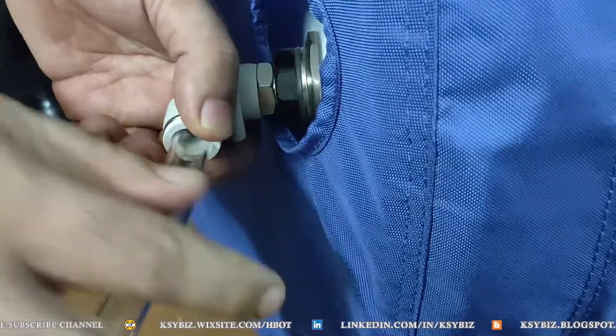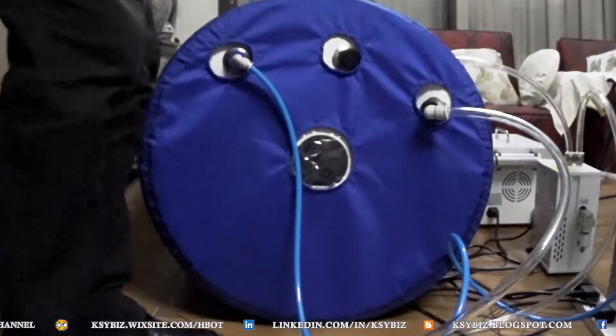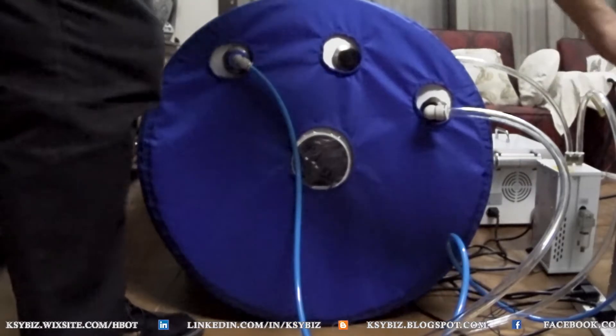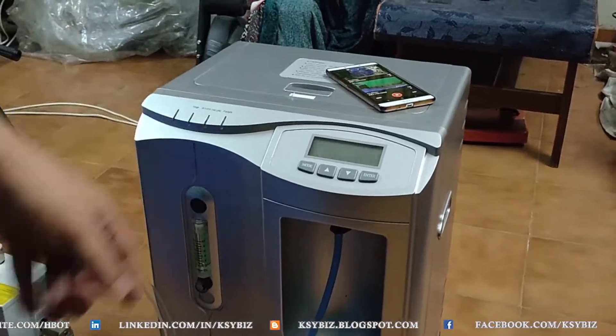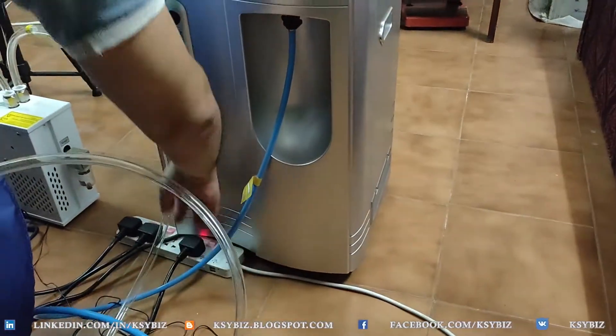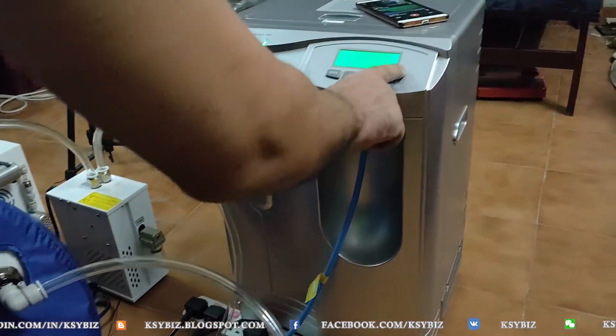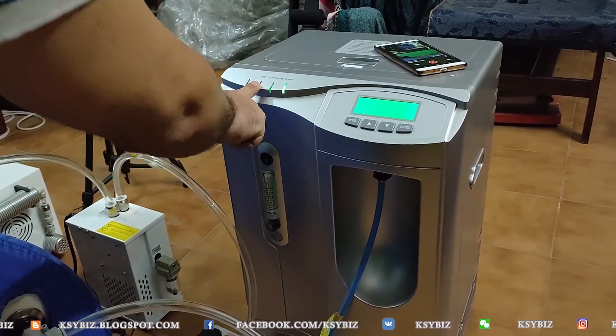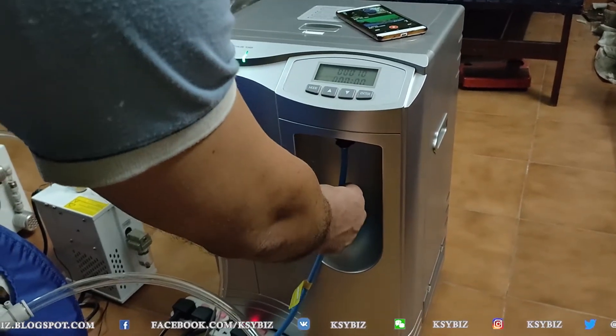Press here and it goes like this. The pipe coming from the oxygen generator — which is here, the oxygen generator — has an on-off switch. Let me turn on the oxygen generator. This is the on-off switch. You can see the light turning on with the power. This is the temperature light — if it gets too hot — and the blue pipe, which signifies the oxygen.